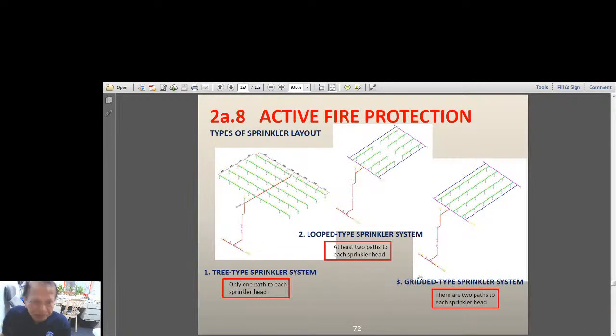So here we have three types when it comes to the arrangement. On the left is the simplest, the tree type, and then of course the loop type here, and then here the grid type. You will take note that with the tree type, when you maintain, let's say, the main horizontal or vertical, the entire system will be shut down. So when you do that, you have to provide fire watch in all locations, on every floor, when you touch this. But if you have a loop type, then you can isolate the one that needs to be maintained, and the others would still have an operating fire protection or sprinkler system. And of course, at the right is the grid type. So you have so many alternatives when it comes to maintaining any portion of the system.